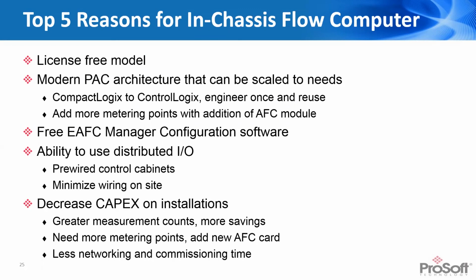It's all based on hardware that fits directly into the Rockwell architecture. By utilizing a modern PAC architecture, that can be scaled to what a producer needs. So they can oftentimes start off with some small skid-based equipment on CompactLogix systems, and as the needs of their well pad site or their operations grow, they can go ahead and scale that to larger CompactLogix systems or even eventually ControlLogix. And because of the use of a single programming environment, Studio 5000, it allows them to engineer once and reuse that. They can build add-on instructions in the system and reuse those in other areas.